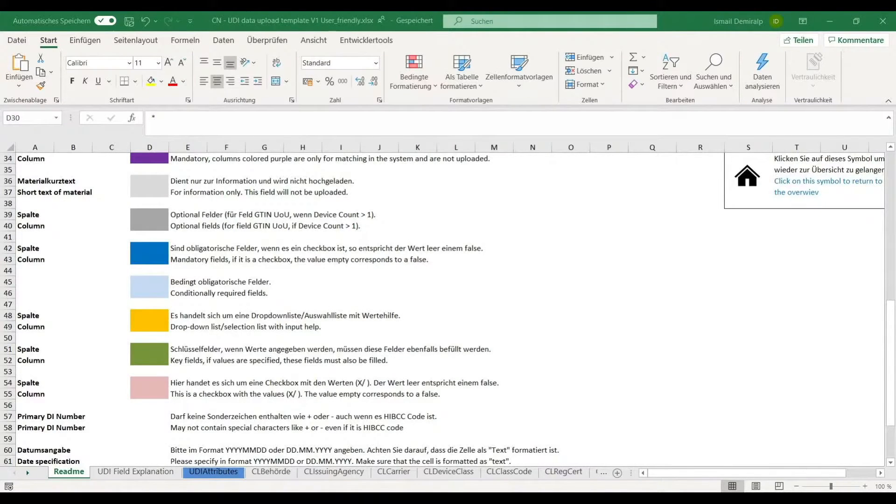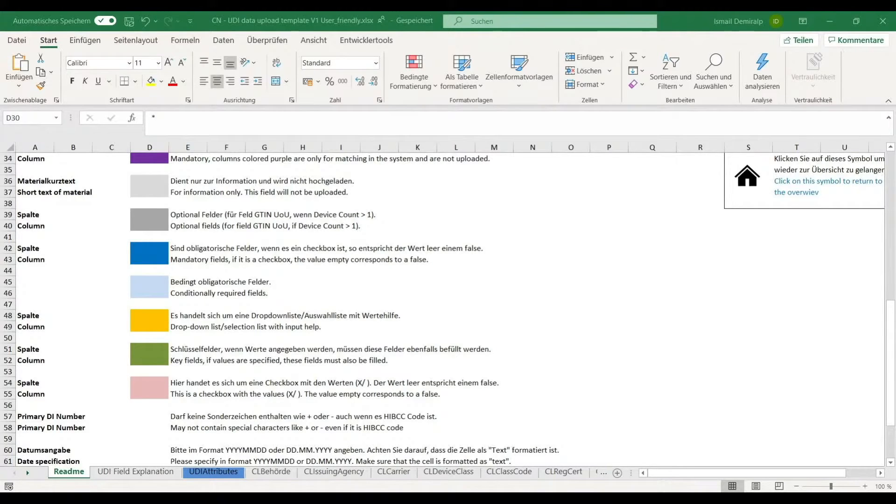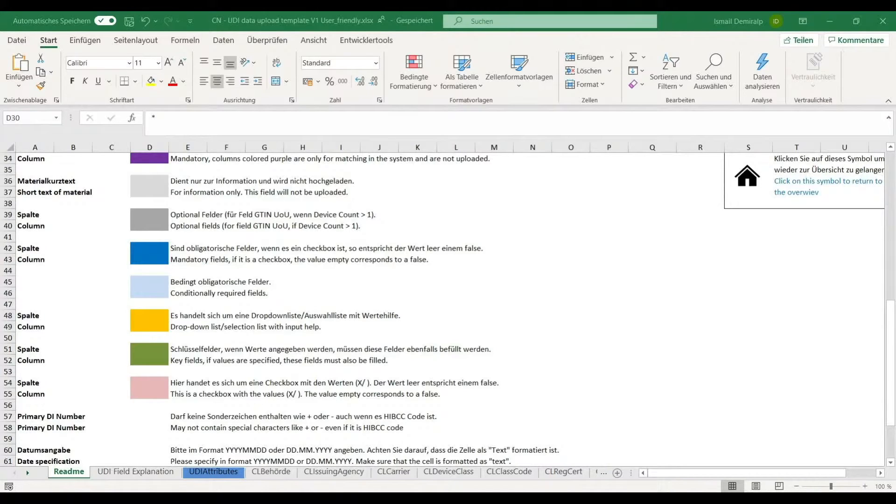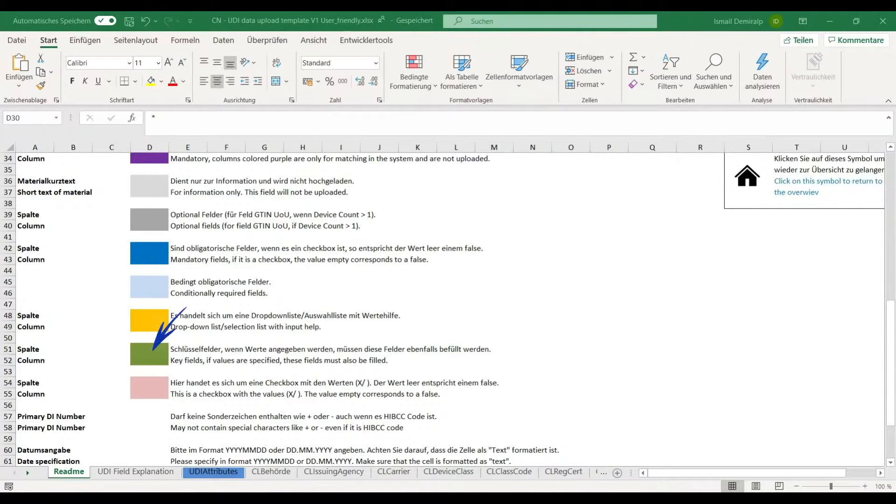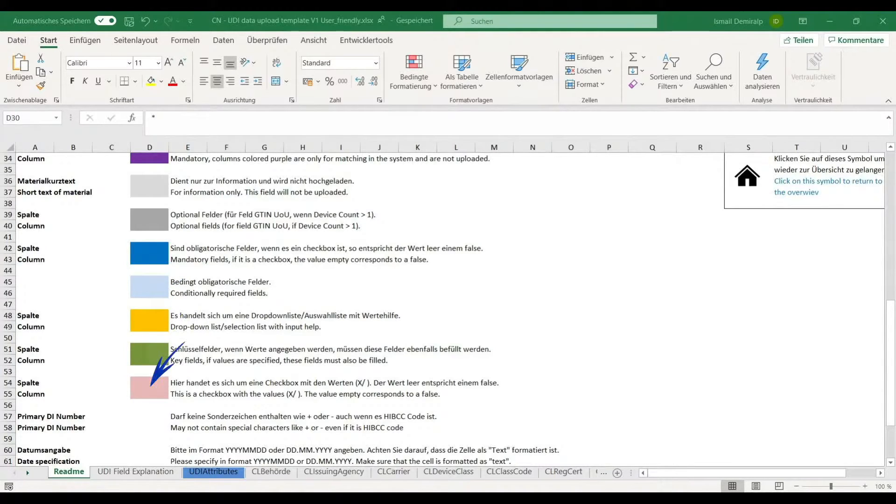You can use our Excel template for uploading data to UDI China database. This Excel template has several sheets. We apply cell color to the UDI China attributes, and on the sheet ReadMe, the color codes are explained. For instance, green for key field, yellow for drop-down list, and pink for checkbox.